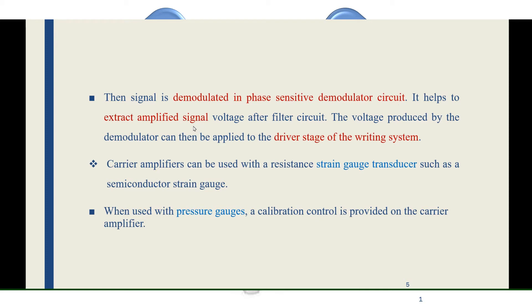Demodulation takes place in the second stage, and after that the signal is recorded using the driver stage of the writing system. There are two types of transducers we can use: the first is a strain gauge transducer and the second is a pressure gauge transducer. If a pressure gauge transducer is used, we have to apply calibration control.